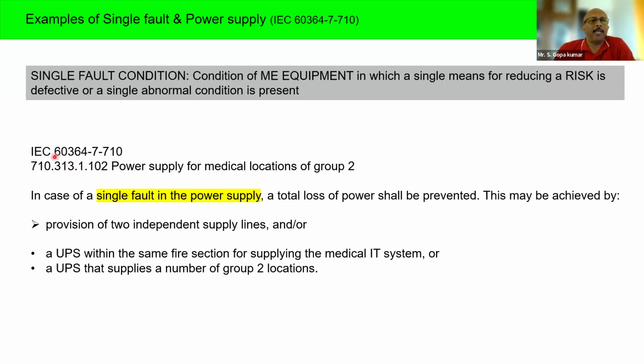Similarly, for the power supply, for example, IEC 60364-7-710, which is our IS 17512 standard, explains that in case of a single fault in the power supply, this is about the power supply, not about the equipment, a total loss of power shall be prevented. This may be achieved by provision of two independent supply lines and/or a UPS supplying the medical IT system.